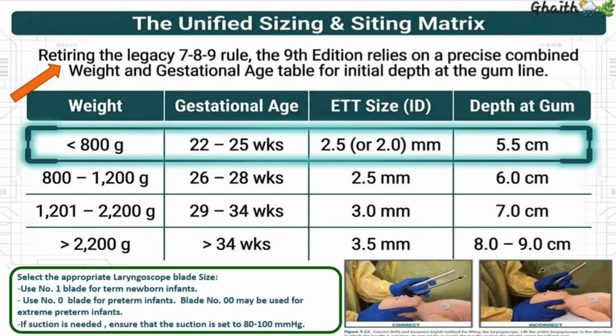For babies under 800 grams, use a 2.5 or 2.0 mm tube at a depth of 5.5 centimeters. For 800 to 1200 grams, a 2.5 mm tube at 6 centimeters. For 1200 to 2200 grams, a 3.0 mm tube at 7 centimeters. And for those over 2200 grams, a 3.5 mm tube at 8 to 9 centimeters.